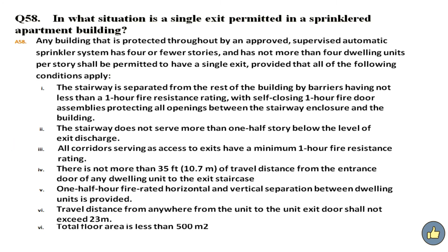In what situation is a single exit permitted in a sprinklered apartment building? Answer. Any building that is protected throughout by an approved supervised automatic sprinkler system, has 4 or fewer stories and has not more than 4 dwelling units per story shall be permitted to have a single exit provided that all of the following conditions apply. Number 1. The stairway is separated from the rest of the building by barriers having not less than a 1-hour fire resistant rating with self-closing 1-hour fire door assemblies protecting all openings between the stairway enclosure and the building.